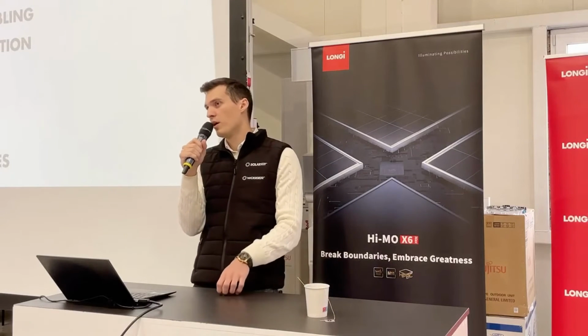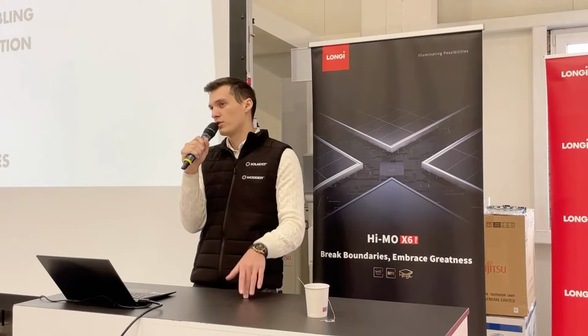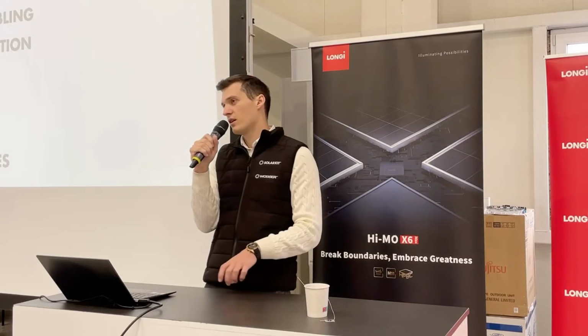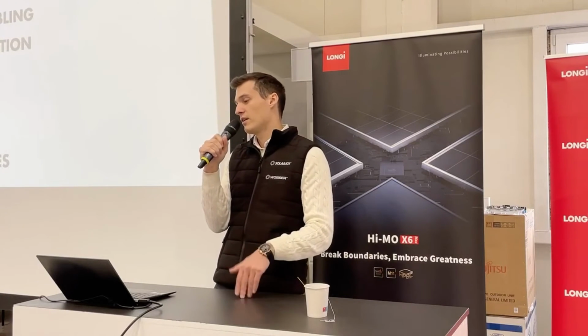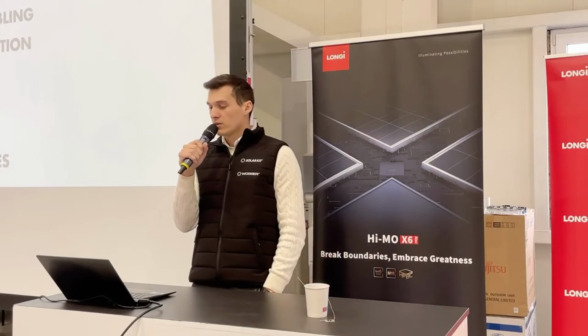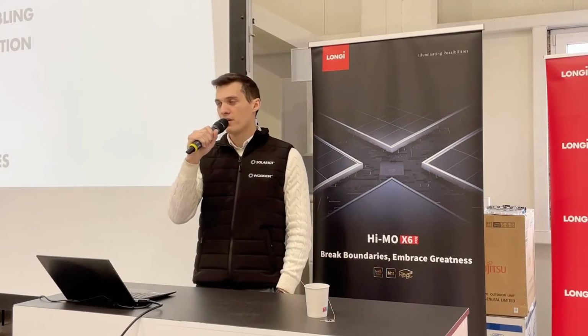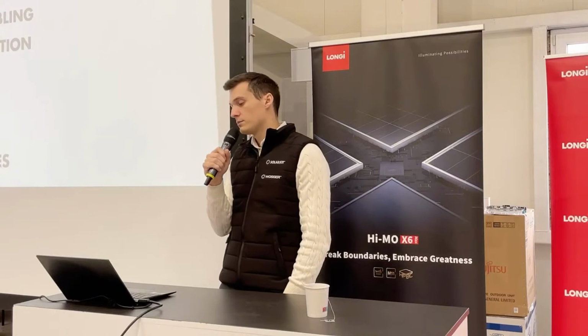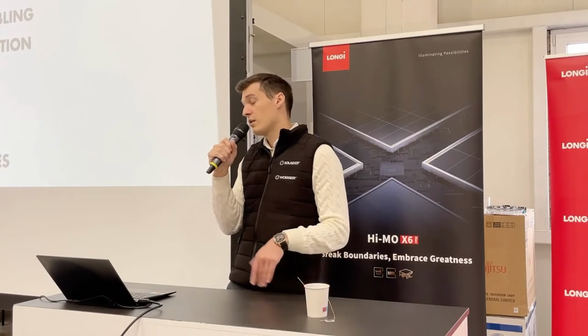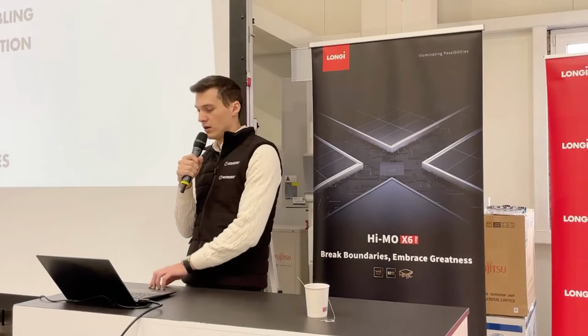So for example, if you buy a Pro V battery, you will have the recommended ampere amount at 50. So for one Pro V, 50 amps. For two Pro V, because they are connected in parallel, 100 amps, and so on. So it will also be 48 volts, but the ampere will increase, or the current will increase with each additional battery. So you need to keep that in mind and size the cable accordingly, because otherwise, if the distance is too long, the cable will heat up, and that could cause a hazard.